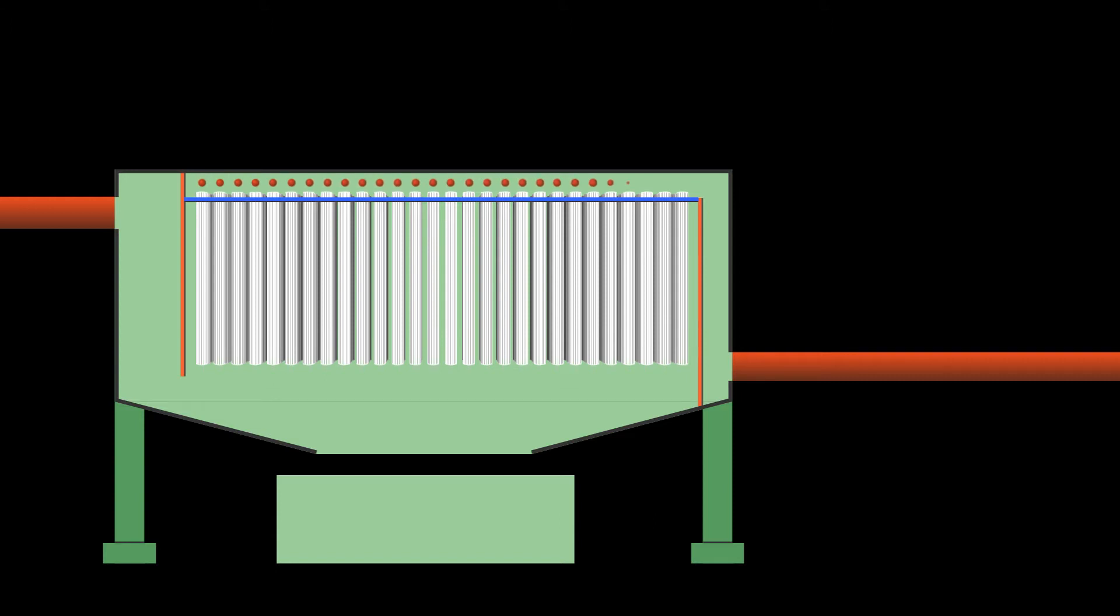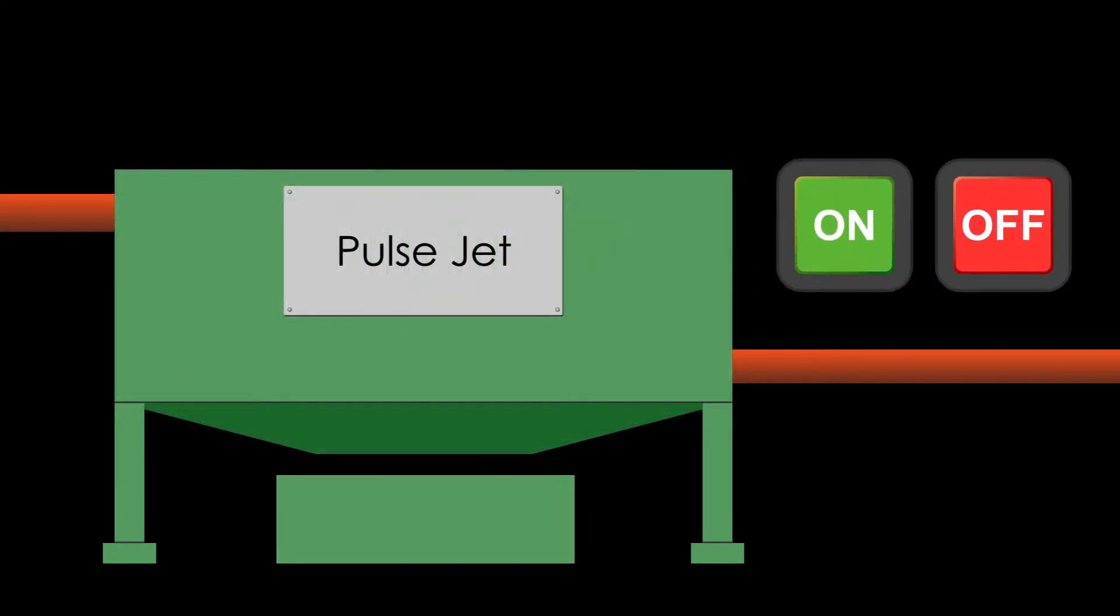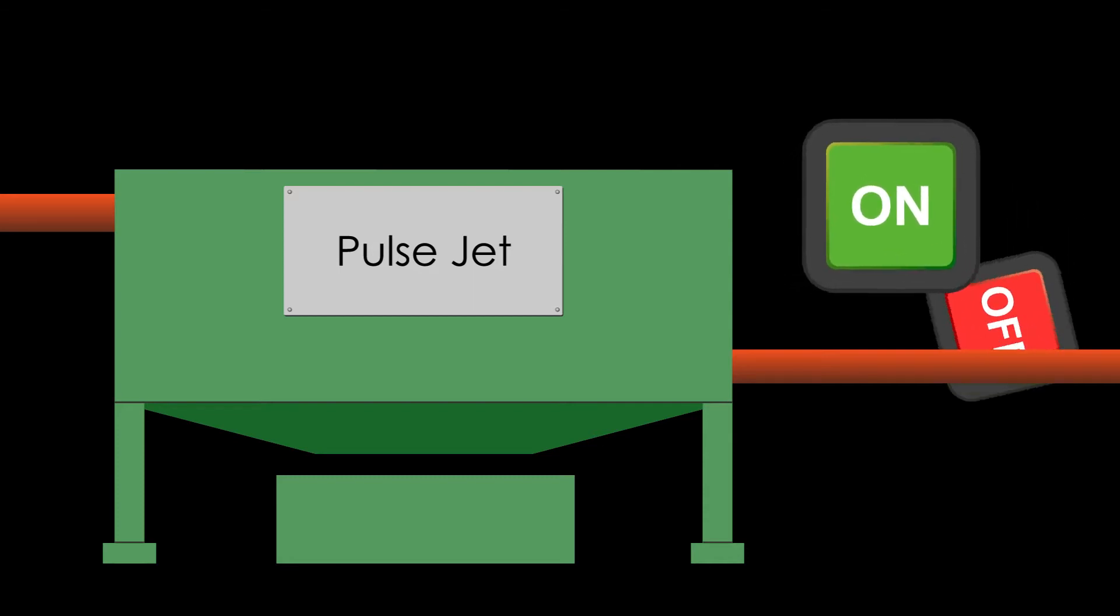When activated, the reverse pulse air travels down the length of each bag in the given row, causing a ripple effect dislodging and releasing the cake dust into the hopper at the base. A main advantage of the PulseJet baghouse is that it does not have to be taken offline to clean the filters.